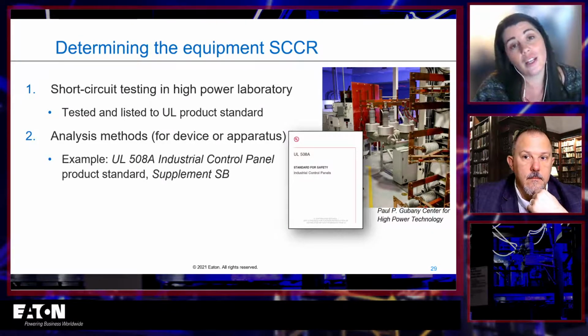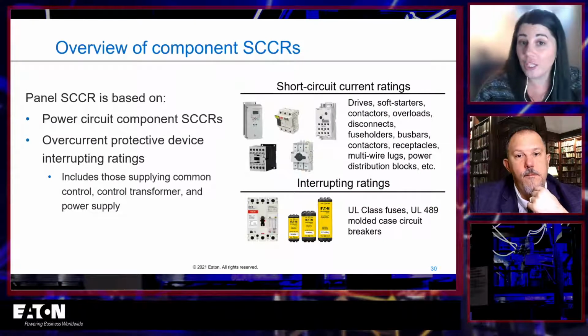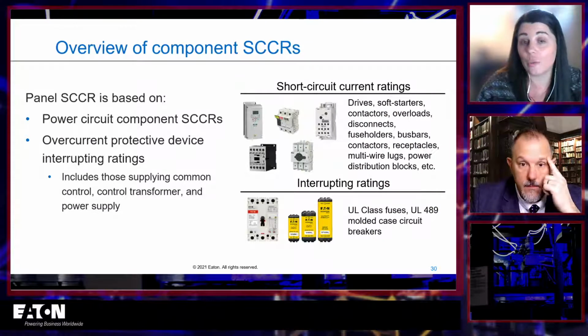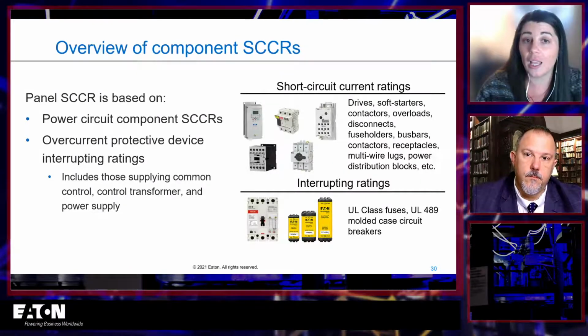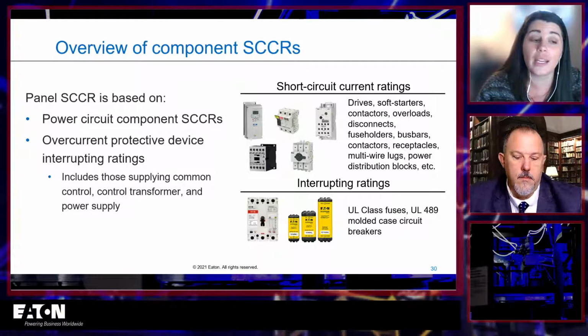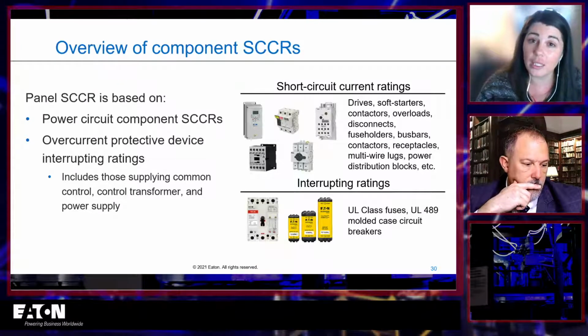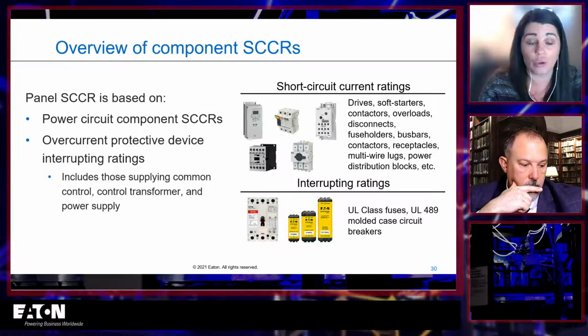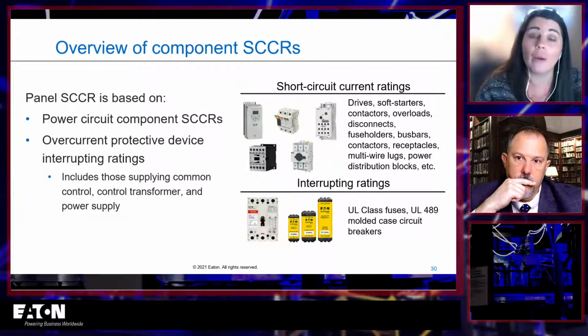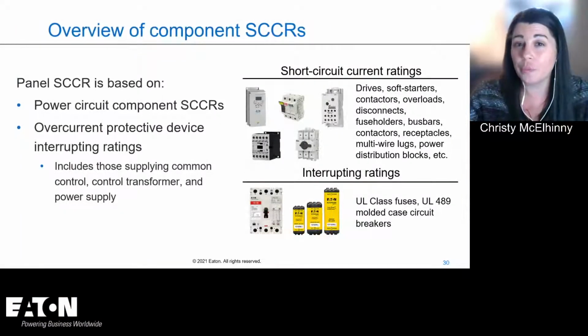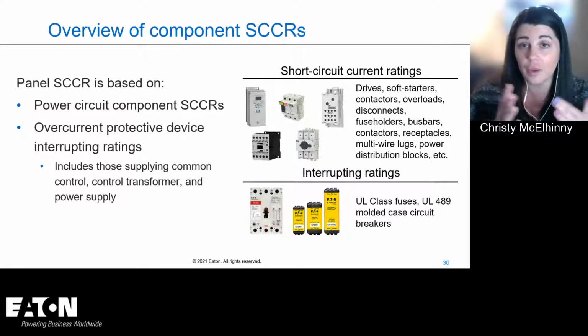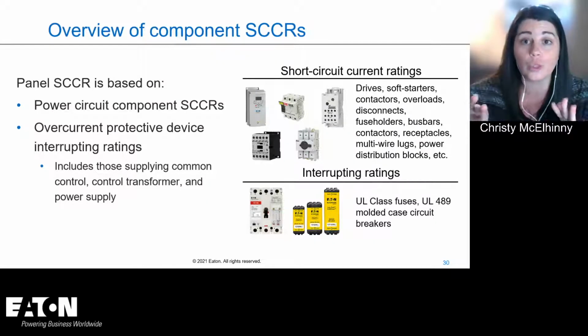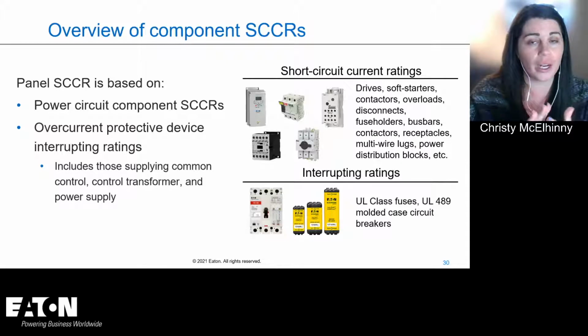So go to the next one, you'll see that whenever we do this, your panel SCCR is going to be based on the ratings of your internal components. And it is going to be based on the ratings of those in your power circuit. I do always like to emphasize that. In an industrial control panel, we typically have both power and control. Power we define as anything that goes to a load, right? So if it goes to a load, we call that part of the power circuit. If it's just electrical signals, that's control. It's inputs, outputs, turn this on, turn this off, close this contactor. That is control. And anything in the control circuit, we ignore when it comes to short circuit current rating.